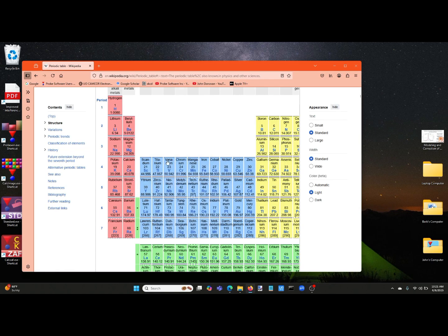And the same goes for vanadium and chromium, chromium and manganese, manganese and iron. The beta line of each of these elements interferes with the K alpha line of the next element up. And the same is true for the second row transition elements, except this time it's the L beta line interfering with the L alpha line.